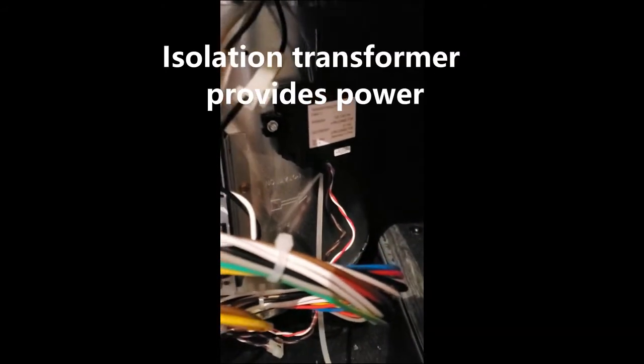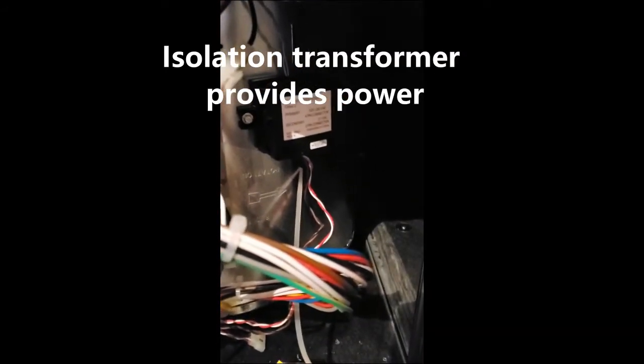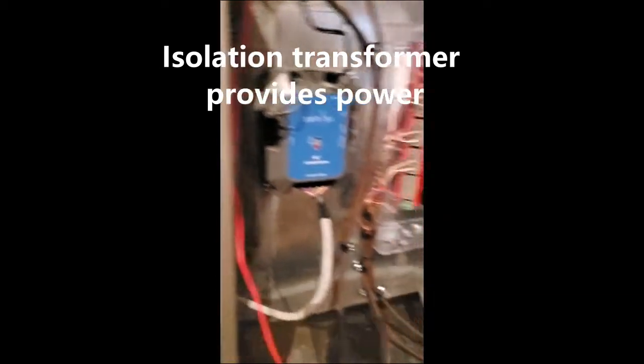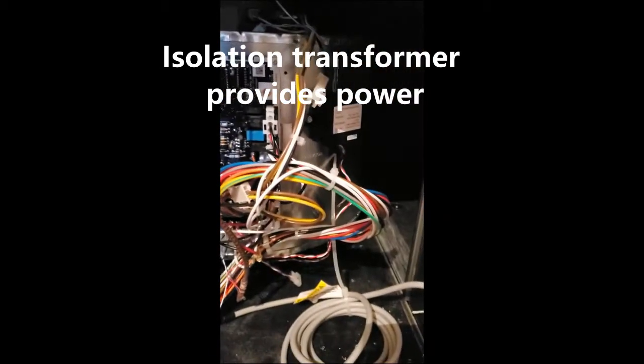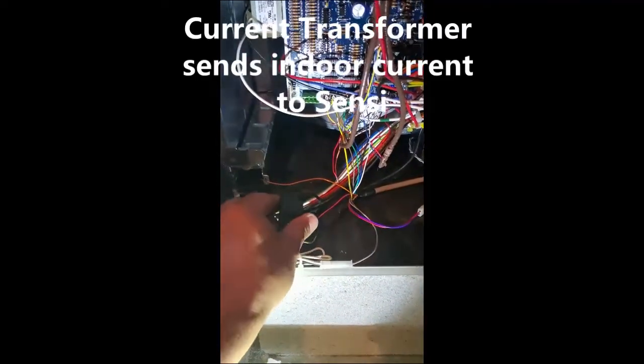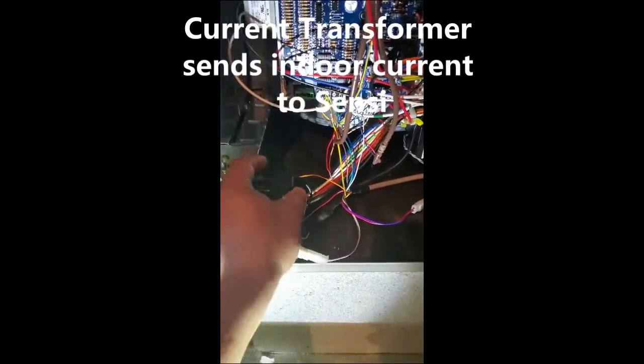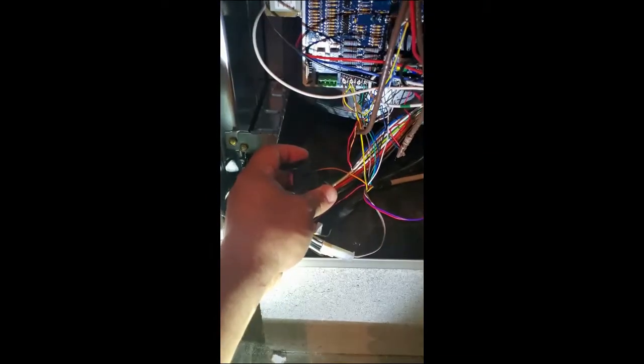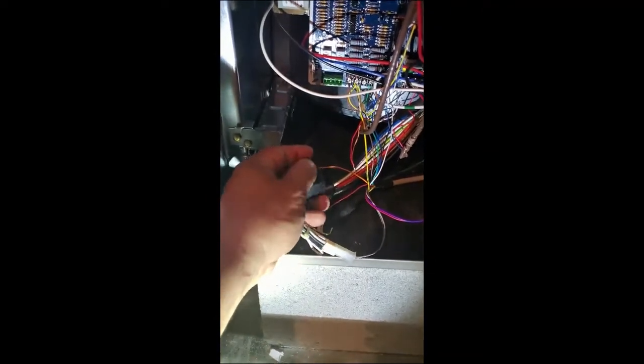Next goes on the isolation transformer, which powers this whole rig, completely separate from the transformer in the furnace. So this is a current transformer, which will sense that the blower is running and devices are running, and give some feedback back to the controller for verification.